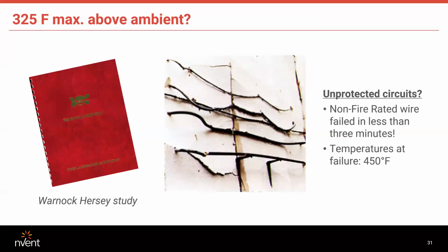And what makes that rather telling is a few years ago, testing was done by Warnock Hersey Laboratories, where unprotected conduit wire was tested, and it was found that the cable failed at 450 degrees Fahrenheit. And what happens is, even when you're using rigid pipe, the heat goes right through the pipe, melts the thermoplastic insulation on the cable, and the cable shorts out against the pipe. And again, that happens at a fairly low temperature, 450 degrees Fahrenheit.